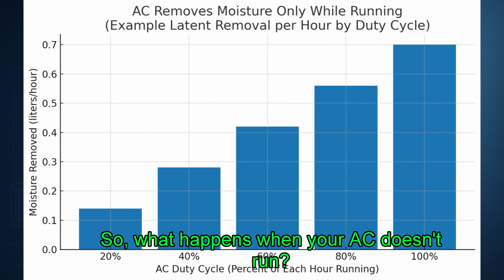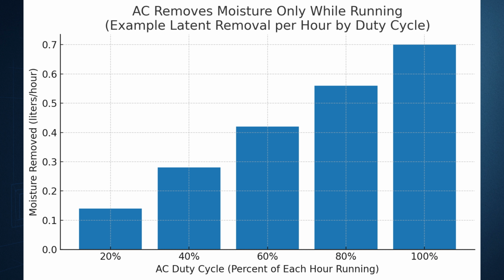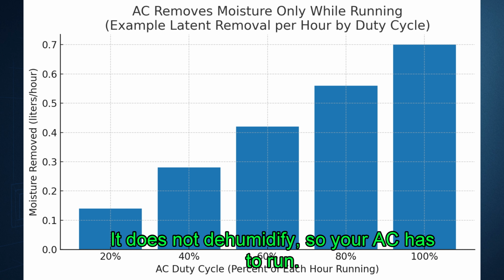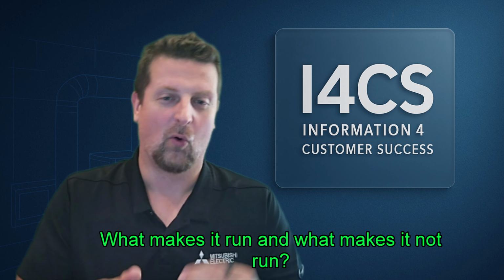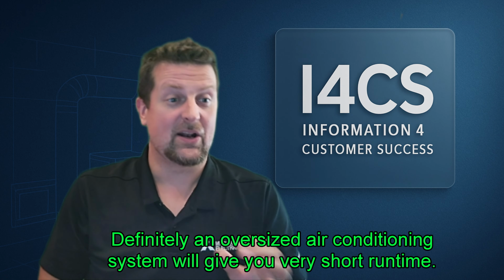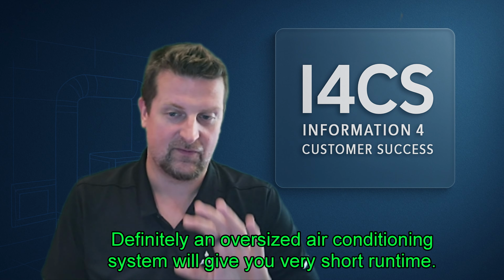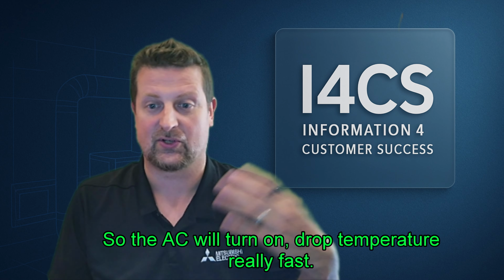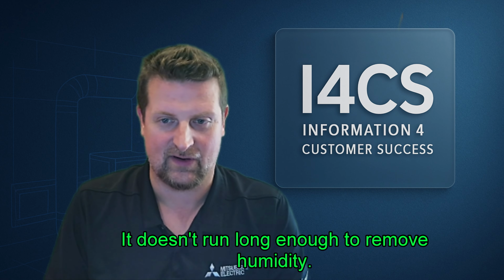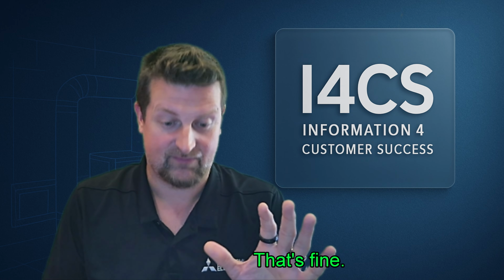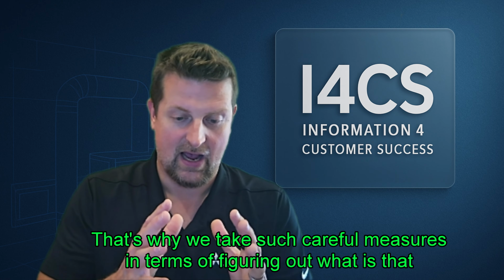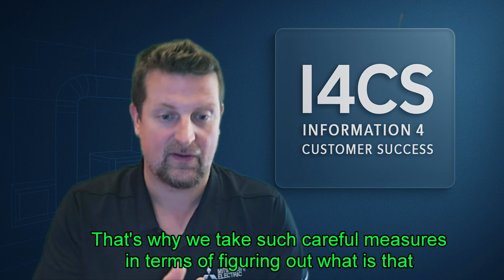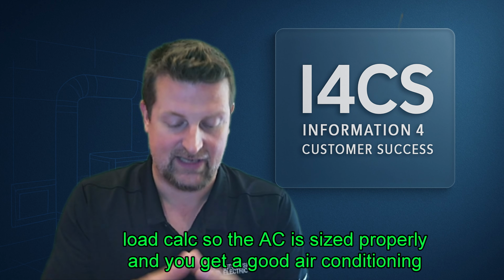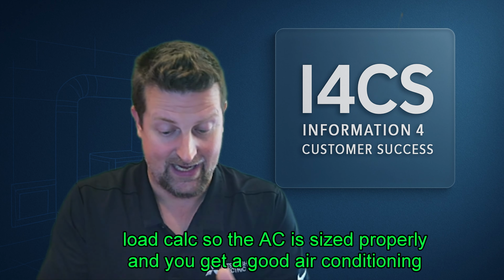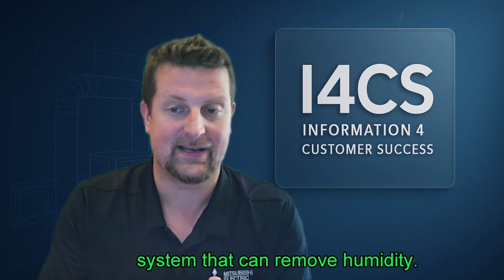So what happens when your AC doesn't run? Well, nothing. It does not dehumidify, so your AC has to run. What makes it run? What makes it not run? Definitely an oversized air conditioning system will give you very short run time. So the AC will turn on, drop temperature really fast. It doesn't run long enough to remove humidity. That's why we take such careful measures in terms of figuring out what is that load count so the AC is sized properly and you get a good air conditioning system that can remove humidity.